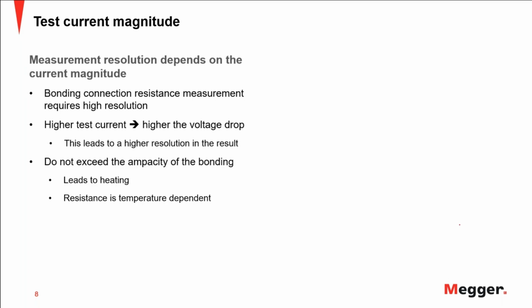However, you cannot use high current indiscriminately, because then you're going to heat the sample, or the surface, or the contact that you want to test. And if the temperature in that surface changes, then the resistance that you're going to measure is going to be dependent on temperature, and you don't want that. So you want to use a current that can give you an accurate result with high resolution, but without exceeding.